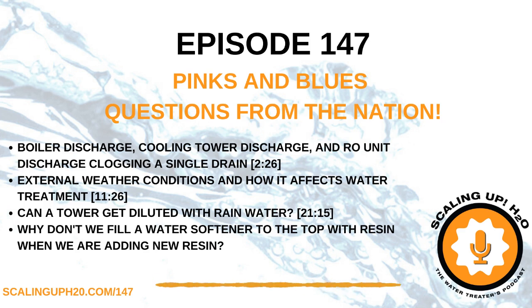What I'm going to do is answer that question with three other questions. The first question is: is the drain clogged? Dirt, debris, and sediment can settle and constrict the pipe size, making the drain unable to handle the water that's coming in, so you have to ask if that's an issue. Also, microbial fouling could be an issue.